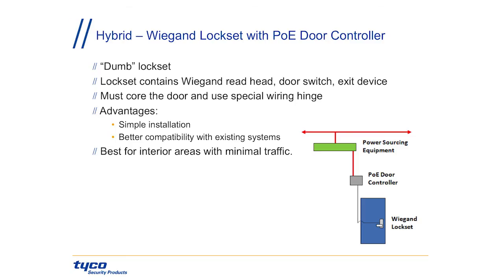A sort of hybrid option is a Wiegand lock set with a PoE door controller — a marriage of the controller with a more traditional lock set that has no database. The lock set has a Wiegand reader, door switch, and PIR built in, but the wiring comes out as traditional leads: six for the Wiegand read head, two for the lock, two for the door switch, and two for the PIR, all wired up to the controller. There are no compatibility issues — these work on old and new systems without software driver concerns. The controller handles the door decision, and the lock set is just along for the ride.